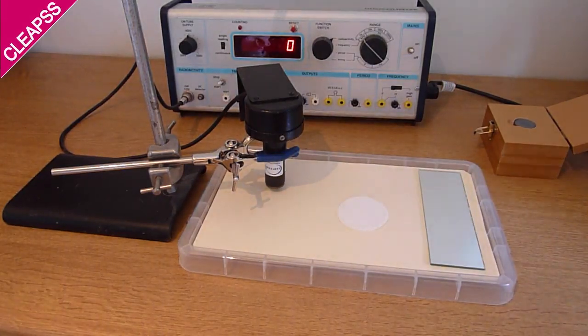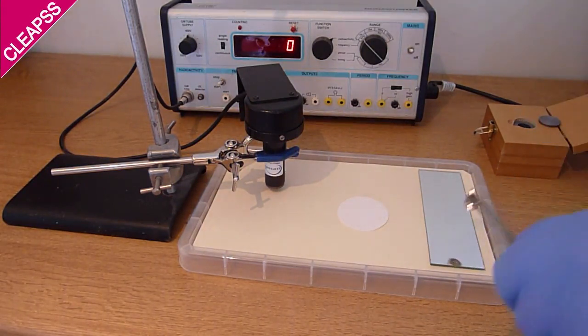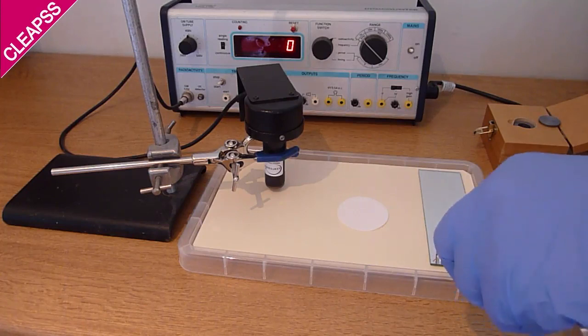Now onto the visual inspection. First examine the foil at the back of the cup. Do it indirectly using the mirror. Check for discolouration of the foil and any other degradation.